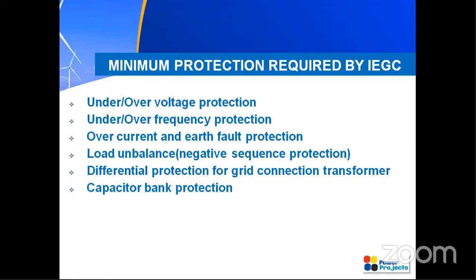One of the main things is the protection required by the Indian grid code. All these are the minimum protection required. Your wind farm should have under voltage and over voltage protection, and under frequency and over frequency protection. Over current and earth fault protection should be there. Negative sequence protection should be there in case of load unbalance. The grid connection transformer should have differential protection. And in type 1 wind turbines, you will be having a capacitor bank especially, so for that you should have capacitor bank protection. All these are the minimum protection required by the Indian grid code requirements, so you have to ensure that you have all these protection systems.